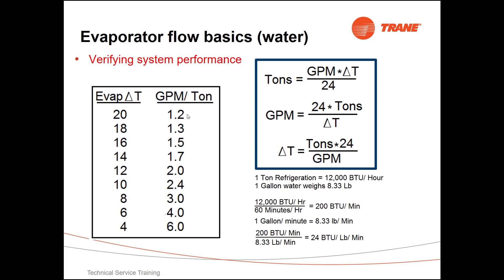So we can see here at 1.2 gallons per minute per ton, that evaporator would do a 20 degree delta T, and all the way down here at 6 gallons per minute per ton, that machine would only be able to produce a 4 degree delta T.